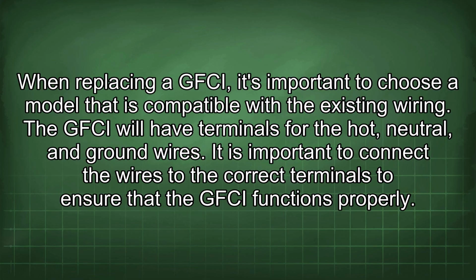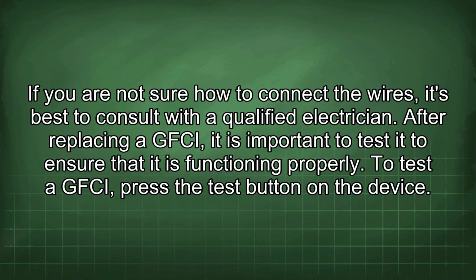When replacing a GFCI, it's important to choose a model that is compatible with the existing wiring. The GFCI will have terminals for the hot, neutral, and ground wires. It is important to connect the wires to the correct terminals to ensure that the GFCI functions properly. If you are not sure how to connect the wires, it's best to consult with a qualified electrician.